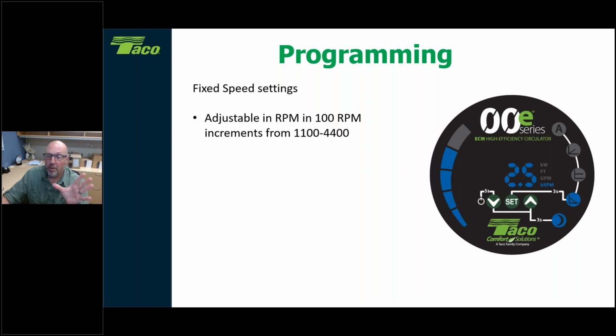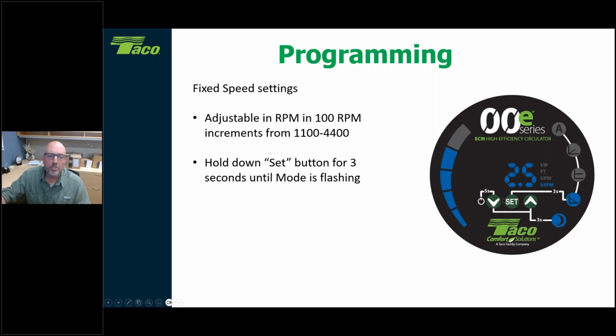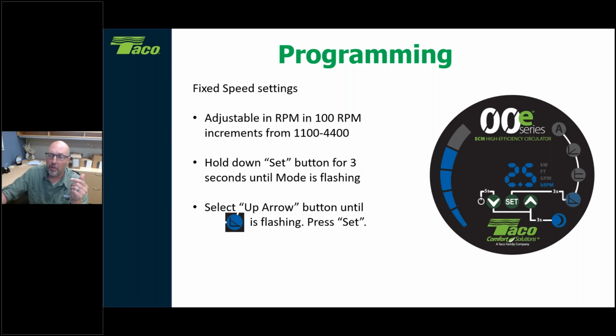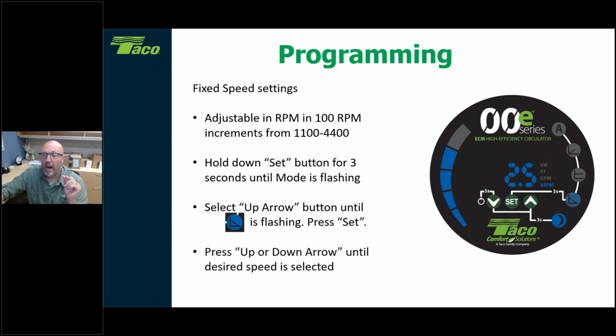But what you need to know in fixed speed mode is your flow and head. Yes, it shows you the gallons per minute, but when setting this circulator up in fixed speed, you need to know your flow and head. You're going to program an RPM, let the circulator run, see what the flow is showing, and then come back and change the speed if you need to. So hold down the set button for 3 seconds, which gets the mode flashing. Once you see the mode flashing, hit the up arrow until the mode that you want is flashing, then hit set again. As soon as you hit set, it gives you the option to change the speed. Right now it's showing 2.5, or 2500 RPM, which is what the circulator is running at. You hit the up and down arrows to change your speed.